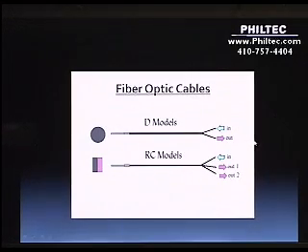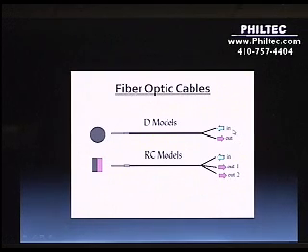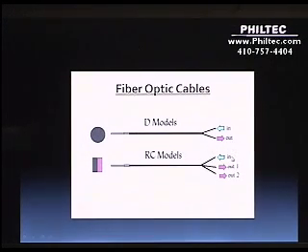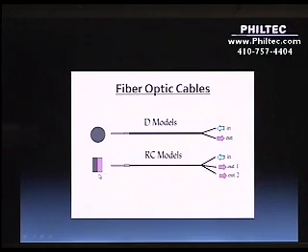In our fiber optic cables we have two types. We have a bifurcated probe for our D models and a trifurcated probe in our RC models. With the D models there's one light circuit. Inside the electronics, light is injected into one leg of the fiber optic bundle. At the sensor tip, the transmit and receive fibers are randomly mixed. Light escapes from the probe, reflects off the target, and comes back into the receive bundle. In the RC models, we have light injected into one leg and light is received in two detector areas. The detector areas in the sensor tip are physically side by side.